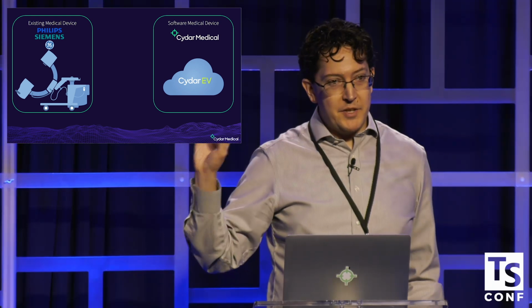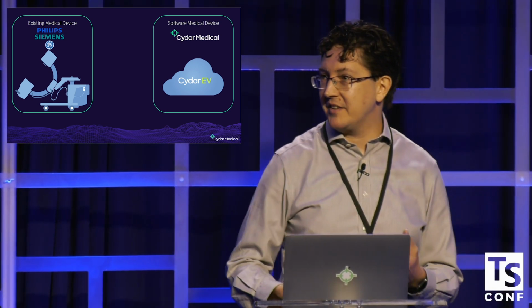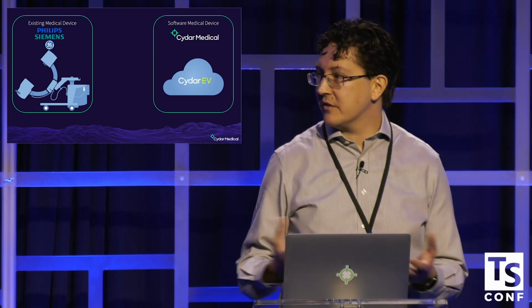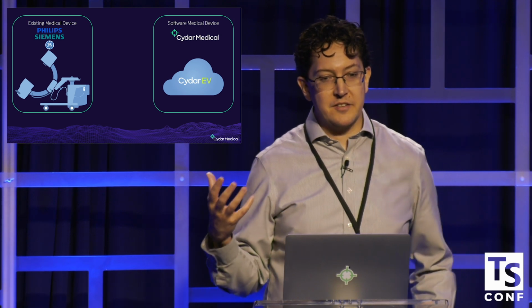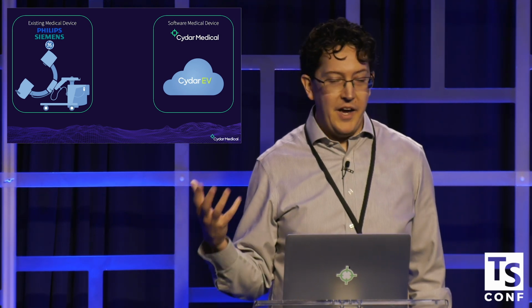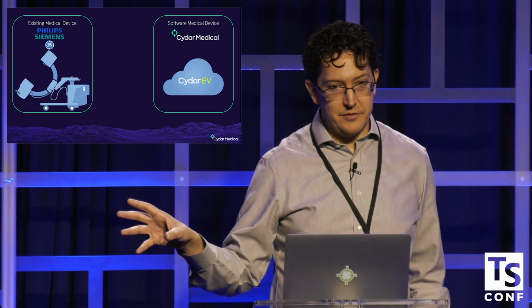And that is a medical device in its own right. We do the certifications for that. That involves having a QMS, a lot of process, and a well-established way of doing things. The key thing is risk assessment, and it's a risk-based approach. So we maintain the certifications for that.